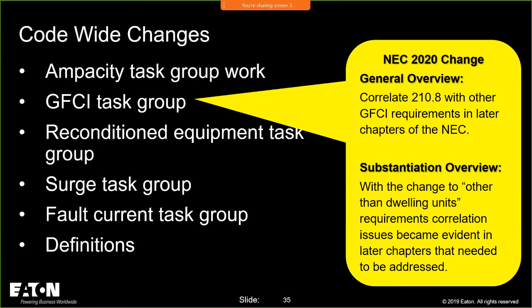What happened was Code Making Panel 2 in the '17 cycle expanded the GFCI requirements beyond 15 and 20 amps. So then we had a correlation issue: back in RV parks, we said receptacles 15 and 20 amps had to be GFCI protected, but in 210.8(B) we said receptacles up to, I think, 50 amps single phase and 100 amps three phase had to be protected. Well, which one do I follow? So a correlating committee task group was put together, chaired by Jimmy Dollard from Local 98 out in Philly. They sat down and said, okay, how do we align these so we're not having this conflict?